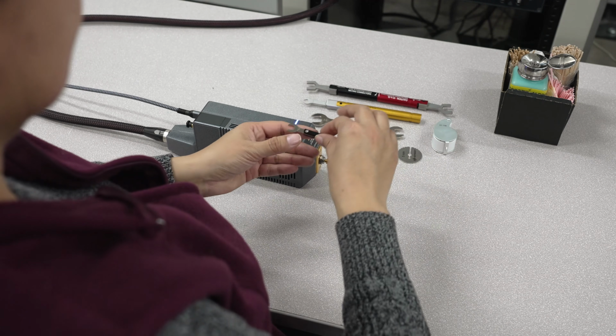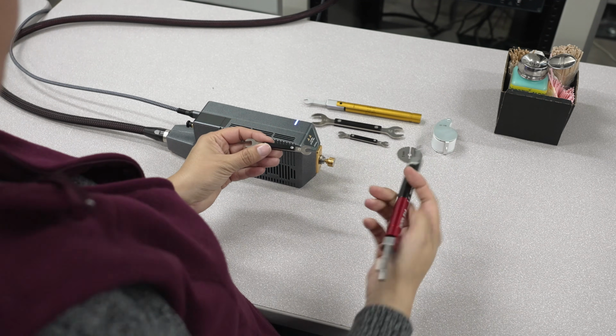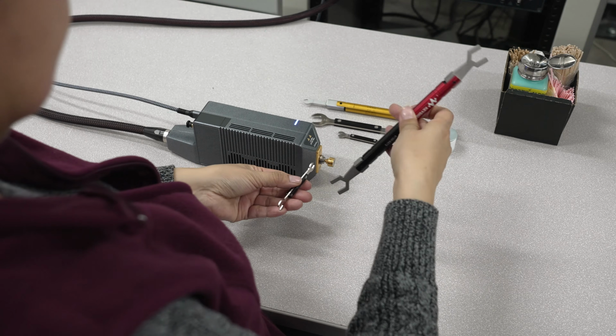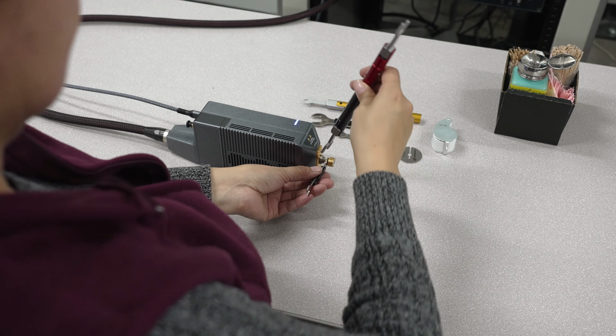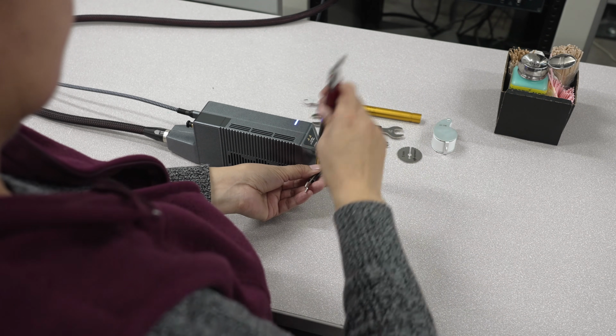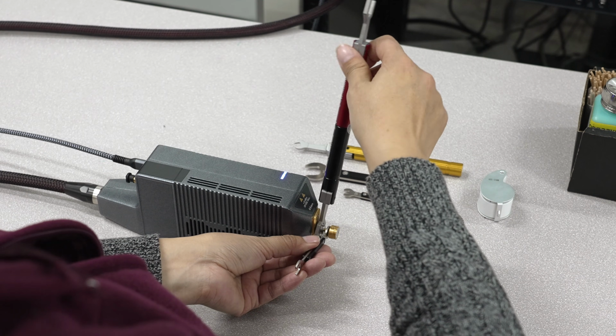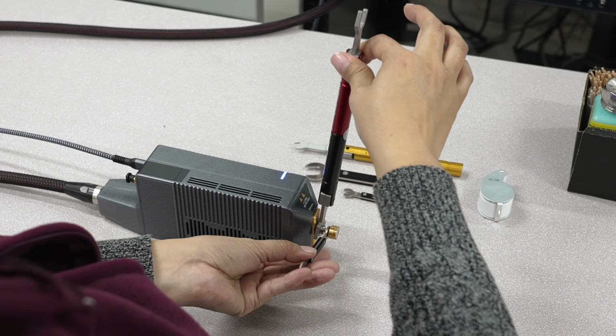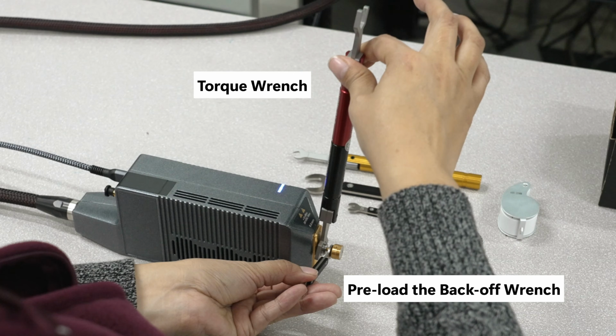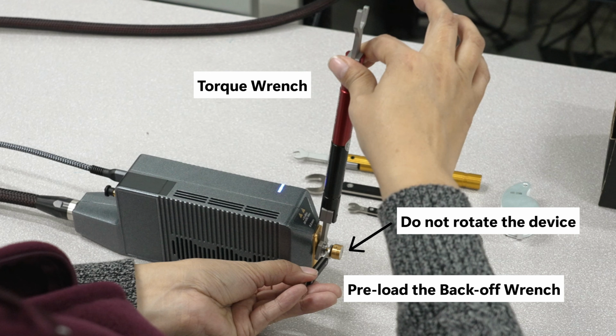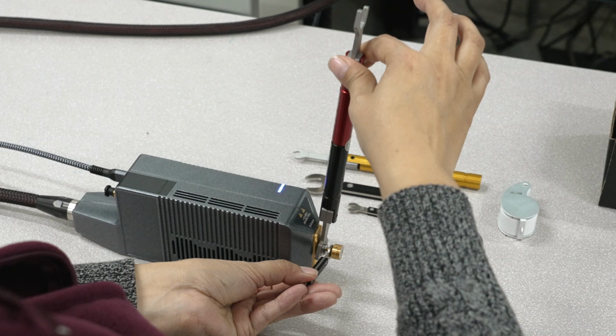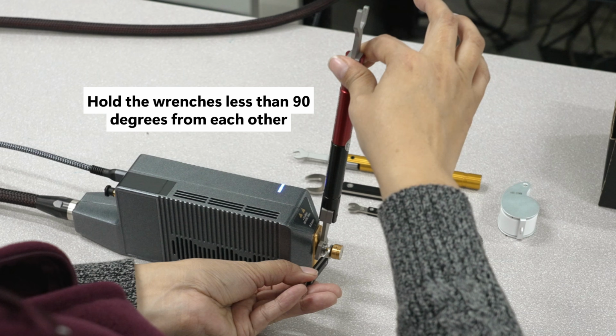Select the appropriate back-off wrench to fit the body of the outer conductor. For all standard devices, use the black 3 pound-inch side of the double-ended torque wrench only. Preload the back-off wrench by applying a light force in the opposite direction of applied torque. This ensures that the device does not rotate, which can cause damage to the mating surface of both the device and the test port. Hold the torque wrench at the designated location and place it on the nut.